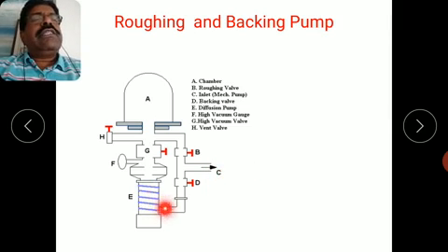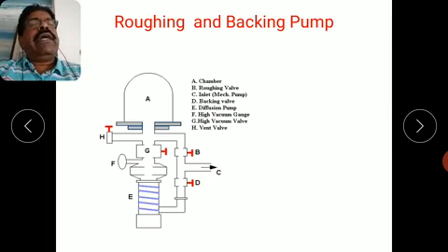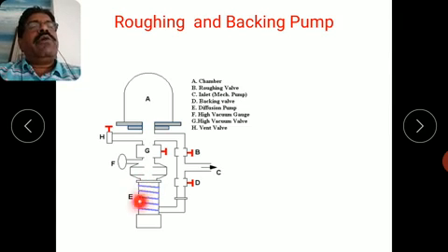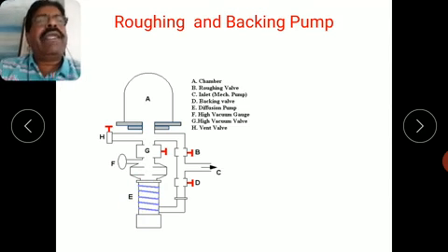The gas molecules evacuated by this high vacuum pump, like the oil diffusion pump, are first of all displaced not directly into the atmosphere but to a mechanical pump where a certain lower level of pressure is present. Therefore the effect of directly transmitting the gas molecules to atmospheric pressure on the performance parameters of this diffusion pump is avoided. That is what the backing pump does.